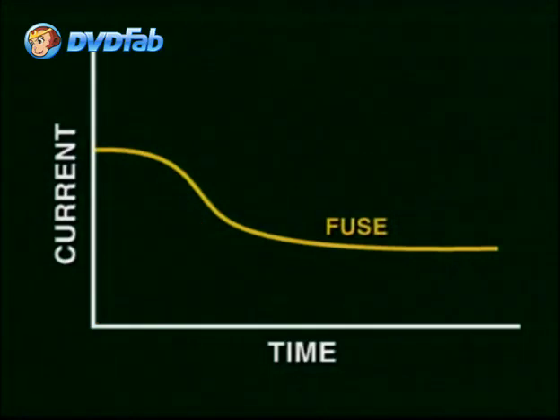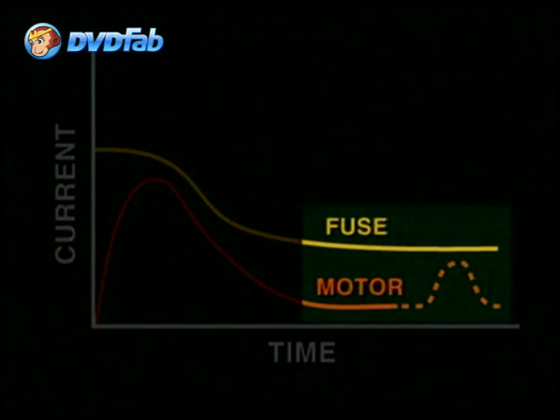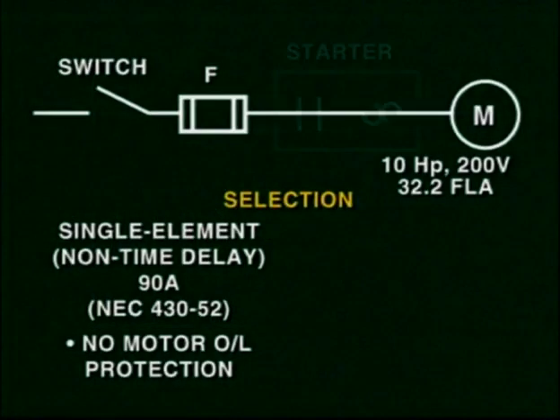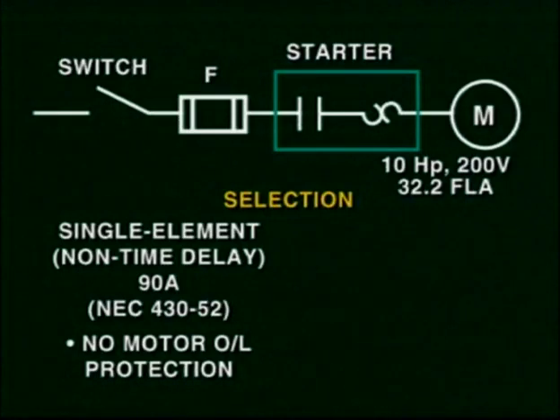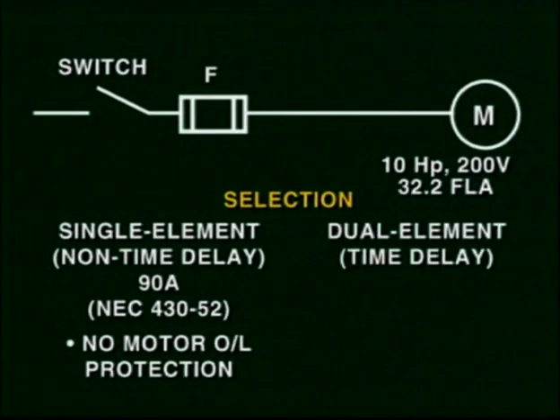Remember that fuses, according to the curves, can allow motors to start if the motor start current curve does not trip the fuse. This 90-amp fuse does not provide protection for the motor under overload. Therefore, it would require overload protection at the starter. If we want to use a dual-element time delay fuse to protect the motor from overload, as well as the circuit from short circuits, we would select, according to Article 430-32 of the Code, a 40-amp fuse.